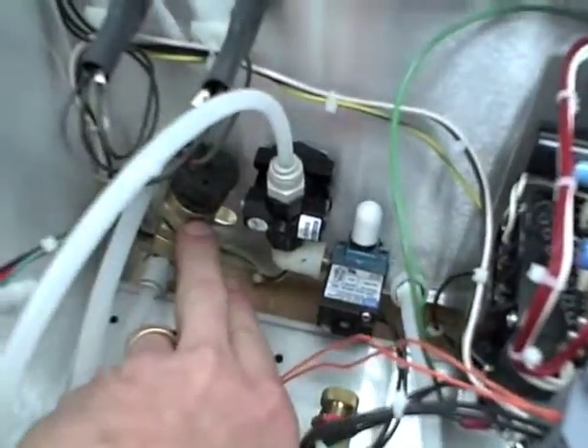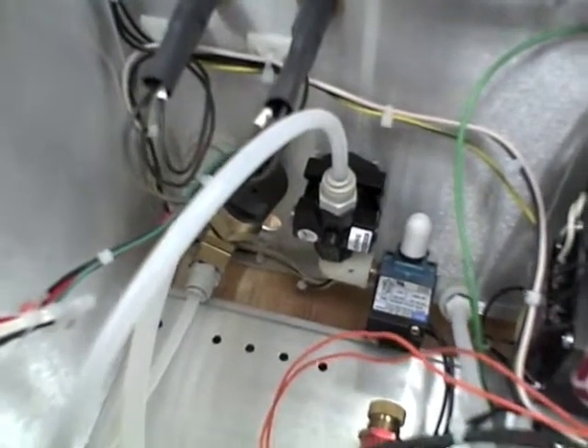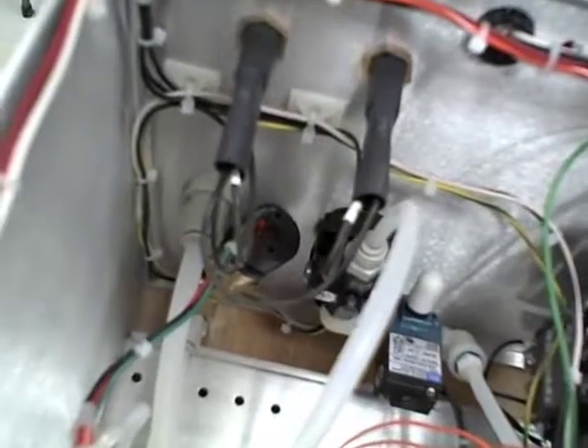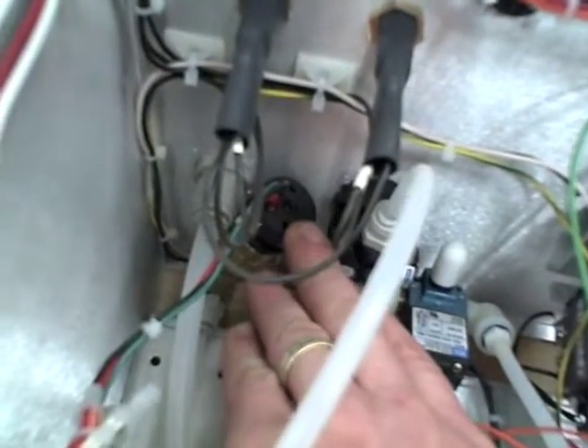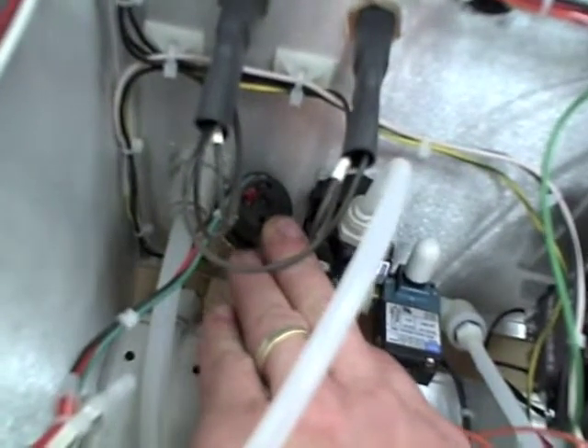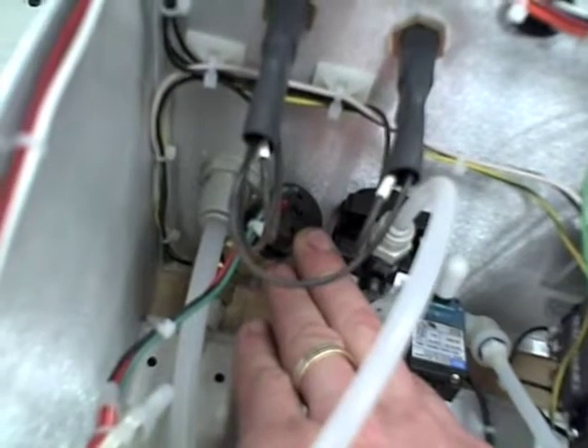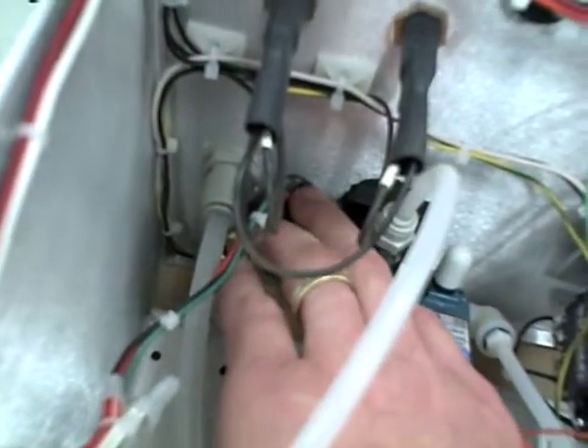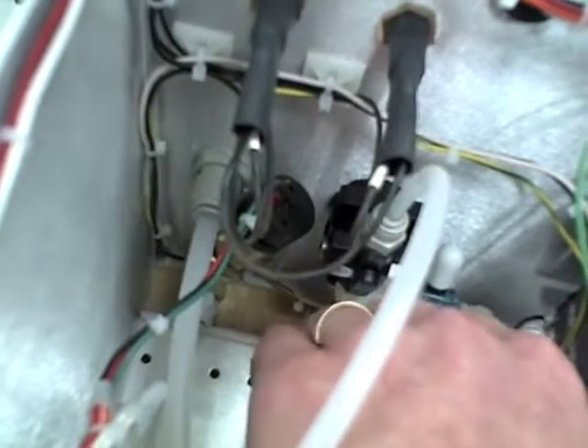If we go around the back of the machine here, we'll see a couple of the fuses, fuse bodies, and then underneath that is going to be the pressure switch. As the machine is powered up, one of the first things that it looks for is 60 psi from the argon regulator, and this is what does that looking. If there's less than 60 psi at the argon regulator, the PLC will see that, and it'll cause a fault to happen. And when a fault happens, then the machine won't operate as normal. It goes into protection mode, and then the only way to get it out of that fault mode is to remedy the fault and then clear the fault.